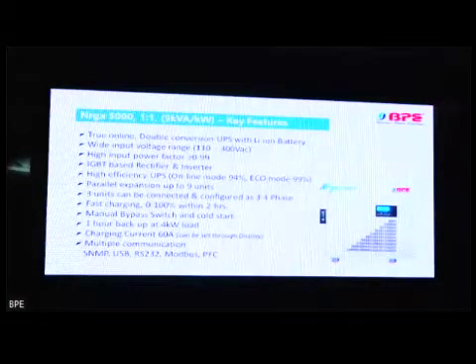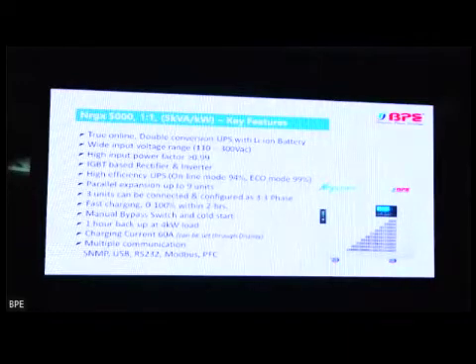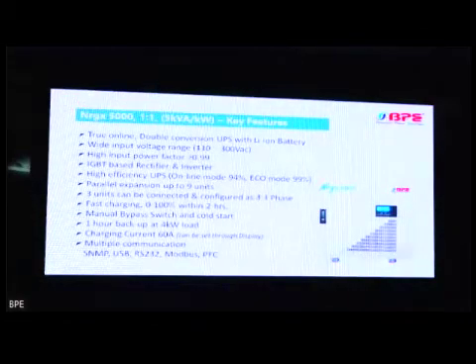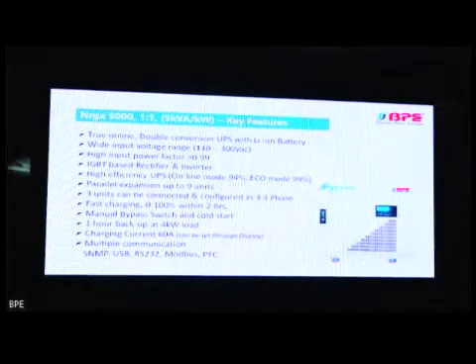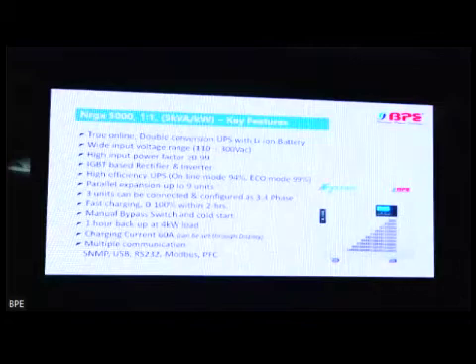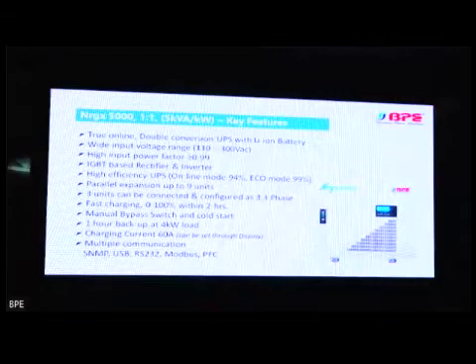Now we have another series, the energy storage systems, which is ESS. So this is our system Nrgx 5000. This is basically 5 kVA, 5 kilowatt, and we can parallel up to 9 such units. So if we use 3 such units of single phase, we can make it, which is also one very interesting parameter. Efficiency of this UPS, online efficiency, if we talk about that, is 94%. Eco mode efficiency is 99%, which is very high.